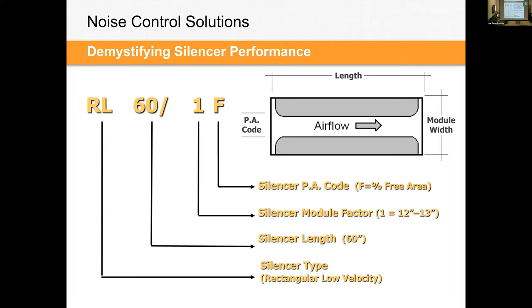What that does effectively is add a lot of acoustic media and sound absorption outside of that duct connection. So your baffle can essentially grow and absorb more sound energy than what the duct size would typically allow. And you usually get a lot of low frequency attenuation with that extended casing because your baffle has grown from maybe, if this was a 12 inch wide silencer, a 3 inch wide baffle. It's now grown to be like a 9 inch thick baffle, a lot of acoustic media there. So that's kind of what it's used for. Okay, is there another question?